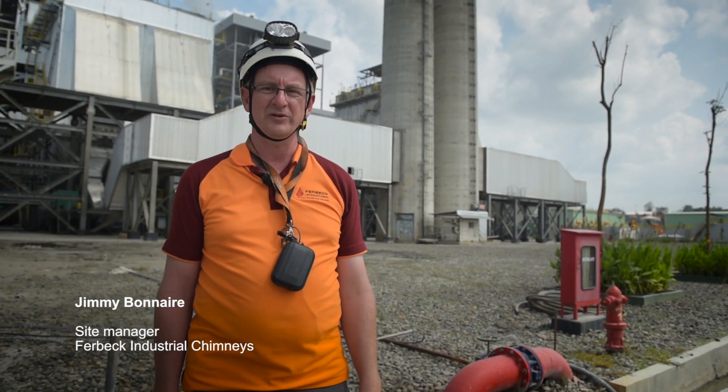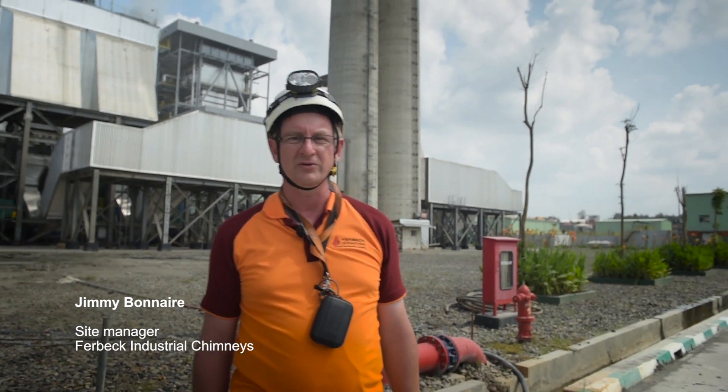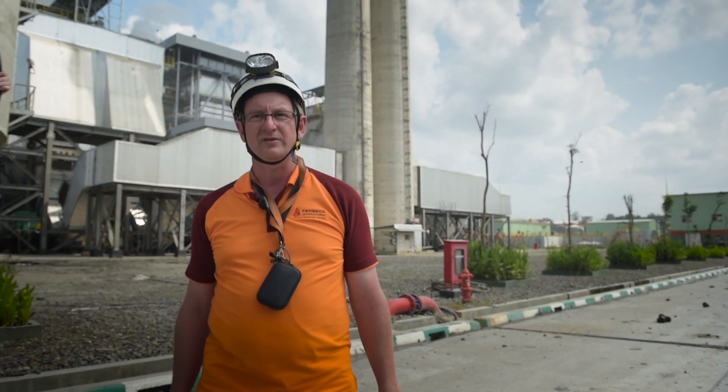Behind me you can see the two chimneys, 130 meters tall, from Kabanagun in Indonesia. During operation at 135 megawatts, the temperature can reach a maximum of 142 degrees. On behalf of Ferbeck, I am here to inspect the Pennguard Block Lining System after two years of operation.